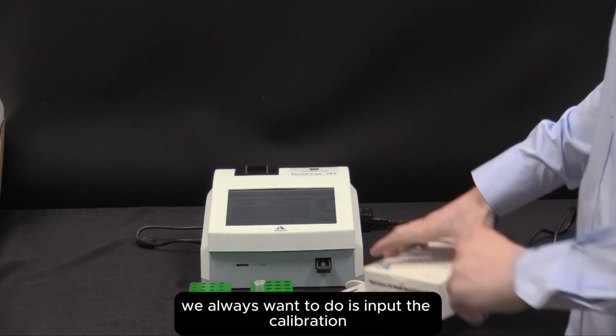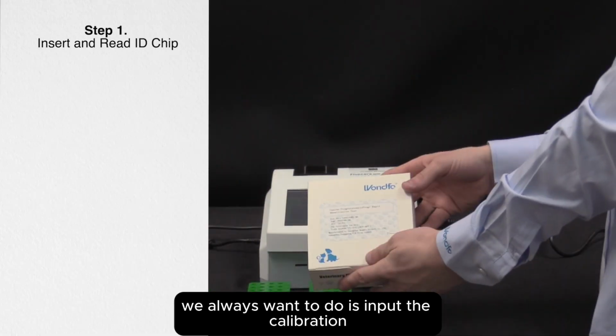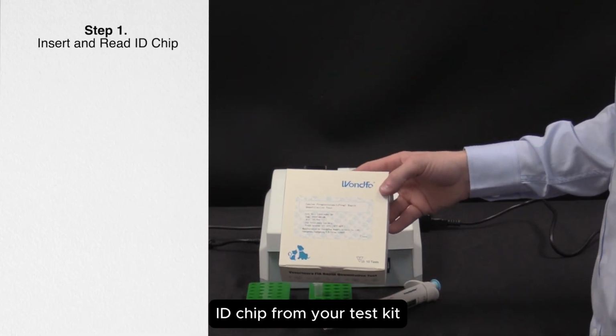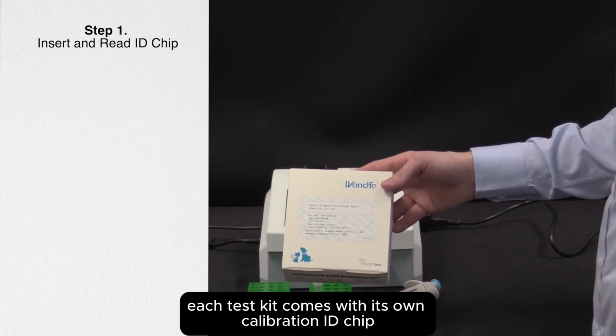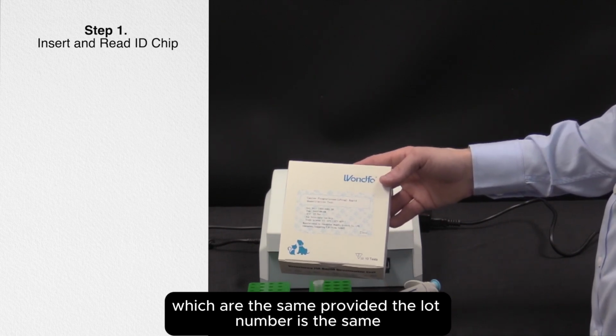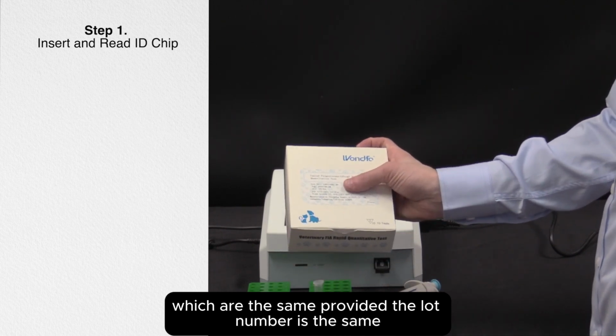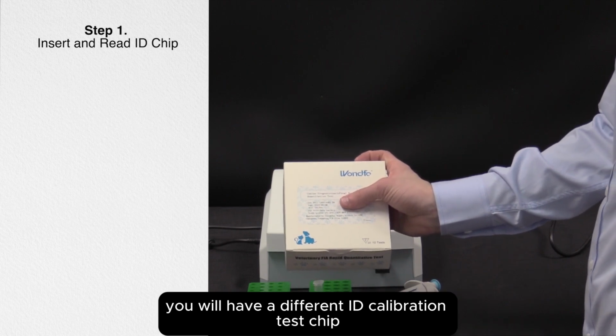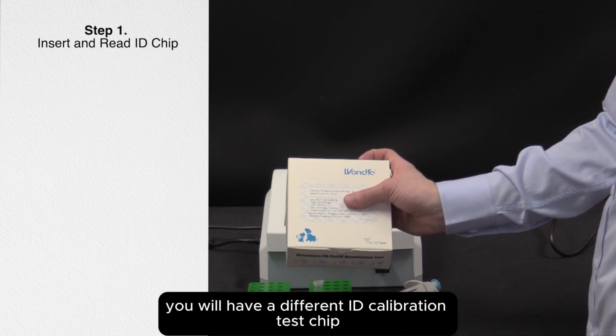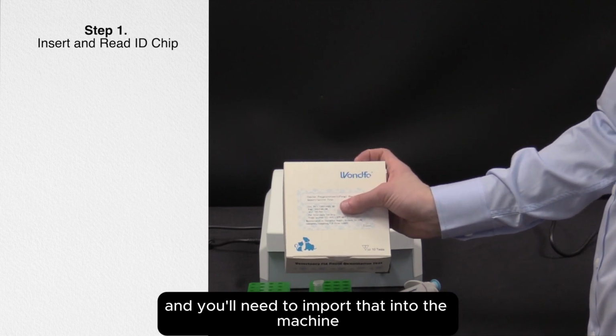The first thing we always want to do is input the calibration ID chip from your test kit. Each test kit comes with its own calibration ID chip, which are the same provided the lot number is the same. So when the lot number changes, you will have a different calibration ID chip, and you'll need to import that into the machine.